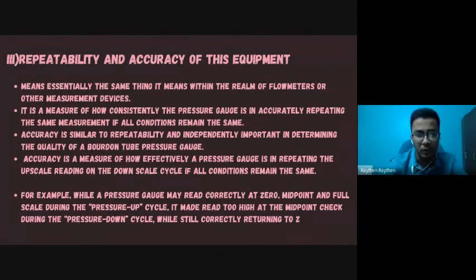Repeatability in the world of Bourdon tube pressure gauges means essentially the same thing it means within the realm of flow meters or other measurement devices. It is a measure of how consistently the pressure gauge accurately repeats the same measurement if all conditions remain the same. Accuracy is similar to repeatability. It's a little more nuanced, yet equally and independently important in determining the quality of a Bourdon tube pressure gauge.